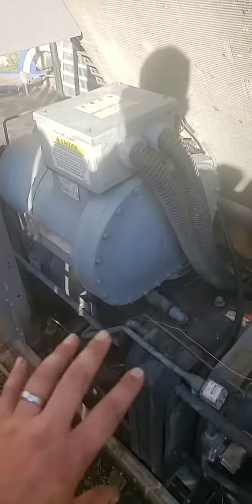If it sees that the water temp on the outlet side is doing a real quick dive and coming down fast, it's going to hold it back. It's not going to let it stage up. So there are a few different conditions that need to be in place before it allows it to stage. Now, the staging is actually done through these two solenoids right here. These are just pressure solenoids, but what they're doing is, there's a slide valve inside here, and the slide valve actually butts up against the screws. Depending on that slide valve's position depends on how much capacity it has.